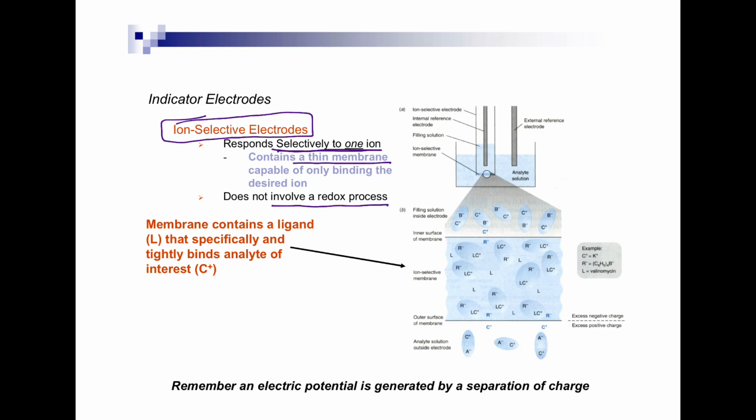The most common type are pH electrodes, which are selective to hydrogen ions. And so they are really good for pH, but they're not necessarily good for if you're trying to indicate silver electrodes or silver ions, something like that.